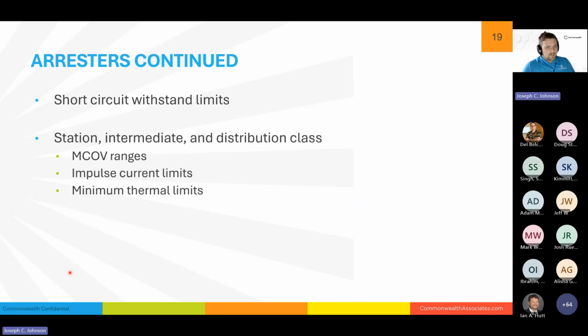So, last little bit on arresters. They are just like any other piece of equipment. They have short circuit withstand limits. They have other considerations, just like any other piece of equipment. And there's three classes that we really work with: station, intermediate, and distribution class. These have different MCOV ranges, different impulse current limits, and that's when you have the switching events or you have the lightning events, and then the minimum thermal limits. A station class is going to have generally higher thermal limits to be considered a station class. And those thermal limits, again, are that energy rating, that kJ per kV MCOV, or Q for coulombs.